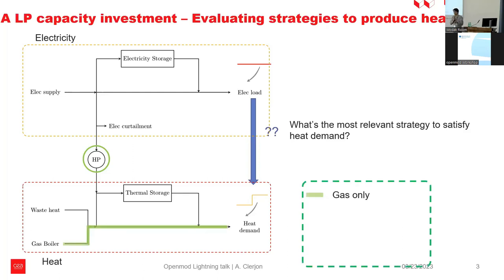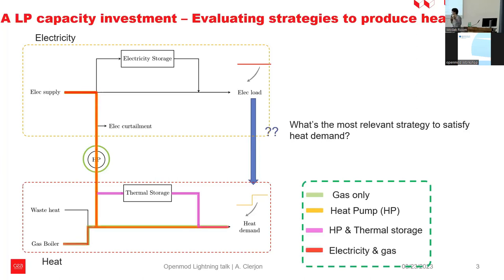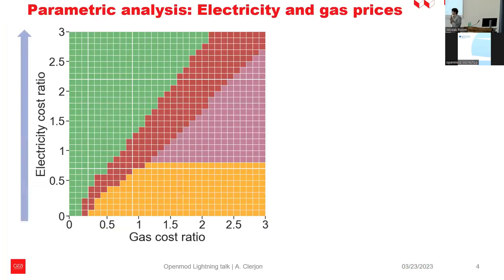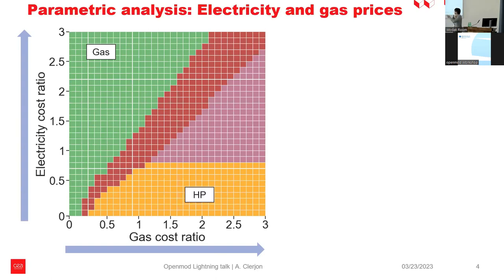There are different strategies. Heat can either come directly from gas production or from electricity through the heat pump. It can also go by the thermal storage, and even come from both gas and electricity. I'm presenting here some results where we're varying both electricity and gas prices. We observe that when electricity cost is rather high, we use only gas. When electricity is cheap, we use only electricity; in the middle, both. And at some point, we can also use thermal storage and electricity.